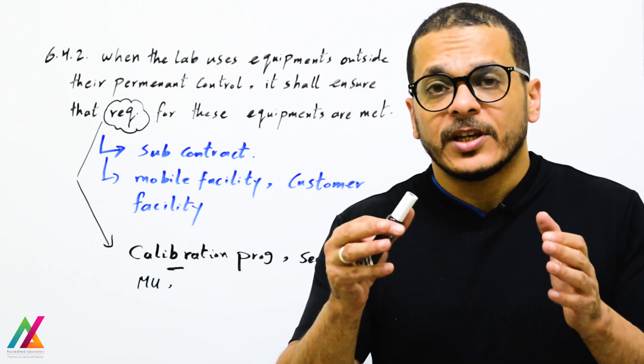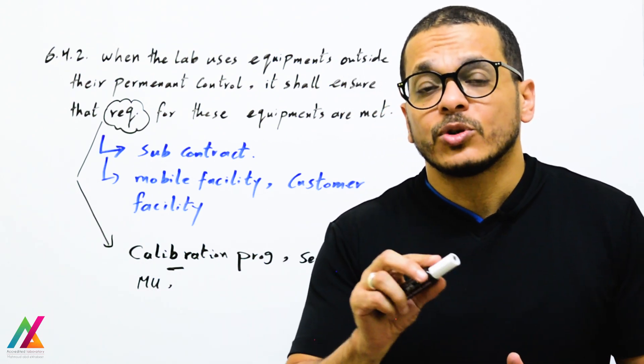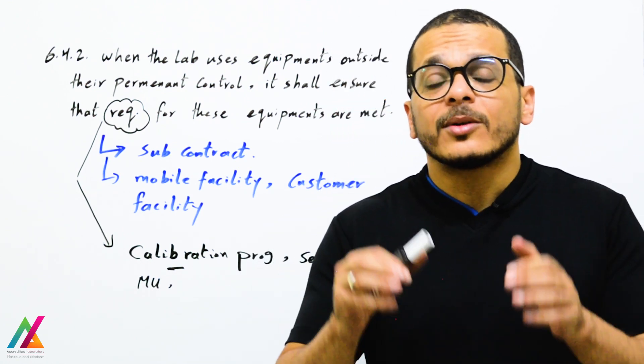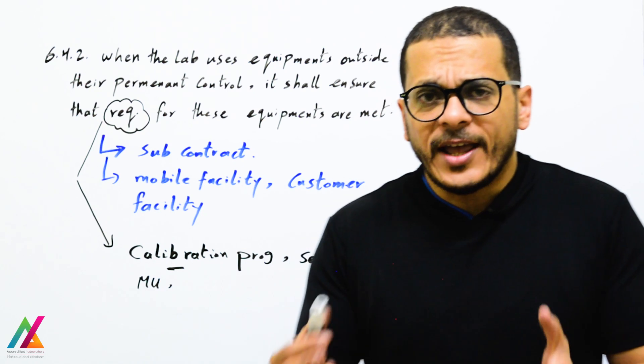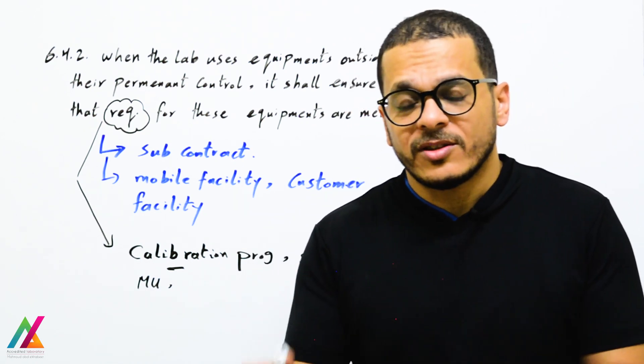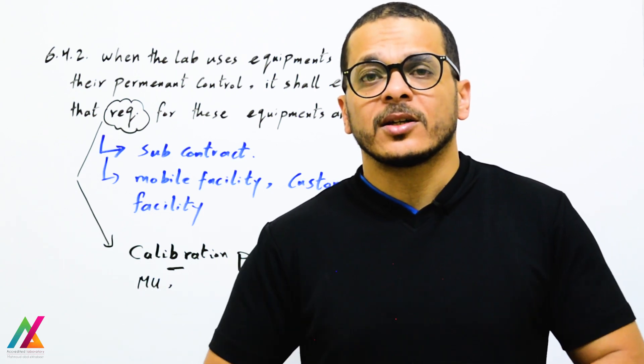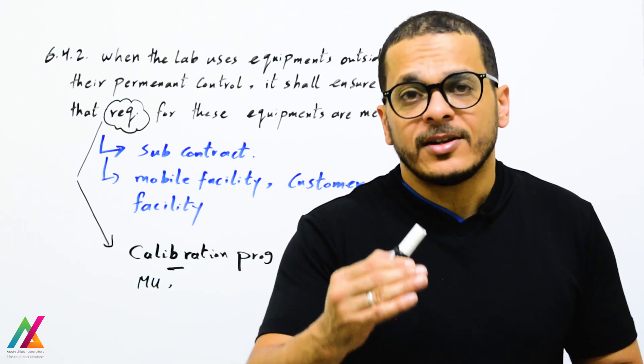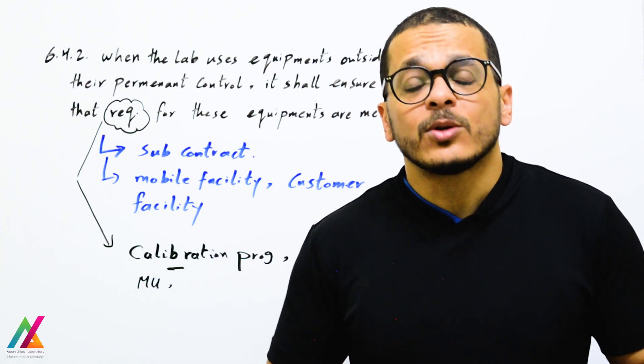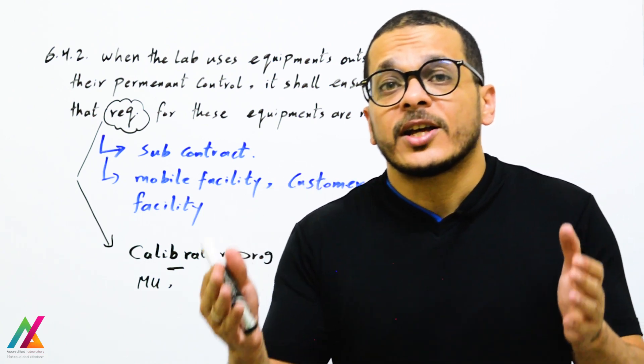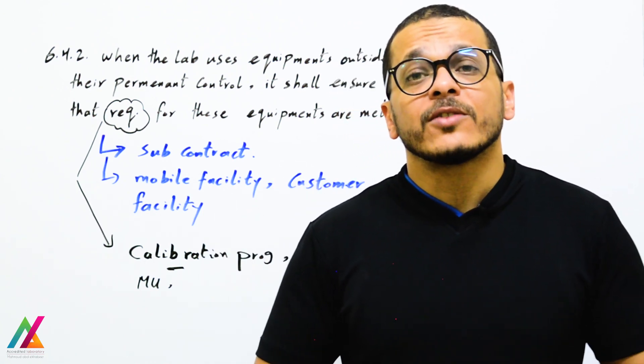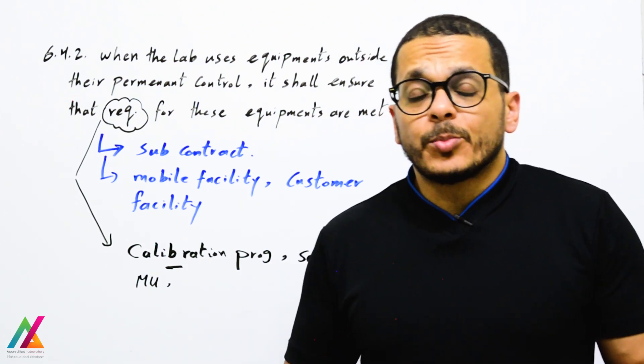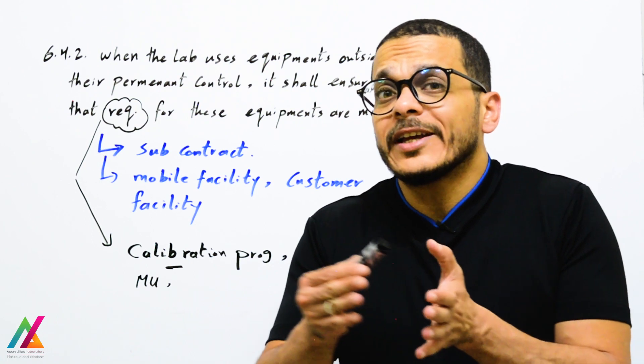The lab shall ensure that equipment not under their permanent control performs well — including checking calibration programs, sensitivity (lowest and highest concentration required for target analytes), and measurement uncertainty. For calibration, acceptance criteria such as a slope ≥ 0.995 and a verification standard within ±10% shall be confirmed. Based on this, the lab shall ensure all requirements are met for all equipment under its responsibility, whether under permanent control or not.